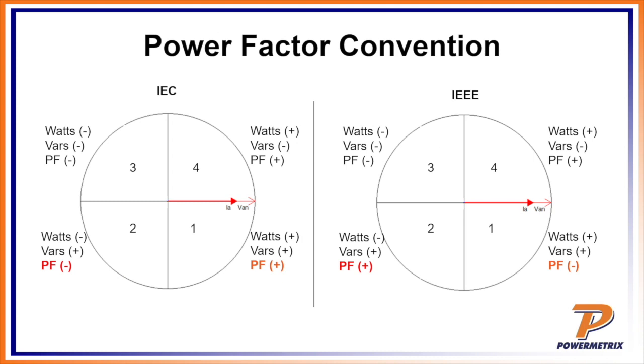So the big difference here is looking at quadrant 1 and quadrant 2. If you look at quadrant 3 and quadrant 4 for a second, notice that everything's the same: negative watts, negative VARs, negative power factor in quadrant 3, and positive watts in quadrant 4. That's fine. But notice in the bottom two quadrants, 1 and 2, the difference between the IEC and the IEEE version is totally different as far as how it puts the sign for power factor.